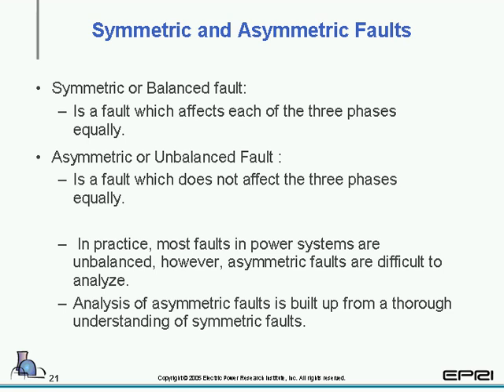The next one we look at is symmetric and asymmetric faults. Simply, a symmetric fault is a balanced fault, which means all three phases see the exact same fault at the exact same time. An asymmetric fault is also known as an unbalanced fault, which means that the fault does not affect the three phases equally. Most of the time, it's a single phase that will see the fault. In practice, most faults in a power system are unbalanced. However, asymmetric faults are difficult to analyze. So most of the manufacturers, when they build the breakers, will do symmetric faults to the breaker, and then through a complete understanding of the symmetric faults, can basically tell what an asymmetric fault will do to the equipment itself.